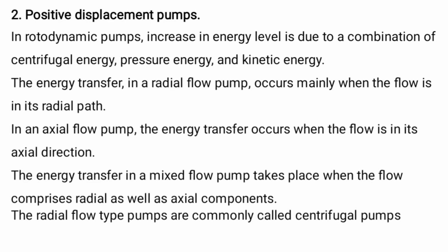In the rotodynamic pump, the increase in energy level is due to a combination of centrifugal energy, pressure energy and kinetic energy. The energy transfer in a radial flow pump occurs mainly when the flow is in its radial path. In an axial flow pump, the energy transfer occurs when the flow is in its axial direction. The energy transfer in a mixed flow pump takes place when the flow comprises radial as well as axial components. The radial flow type pumps are commonly called centrifugal pumps.